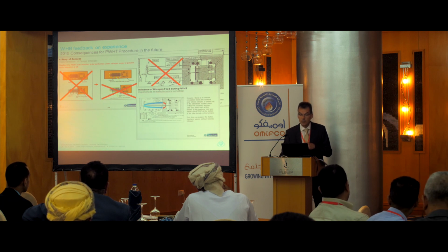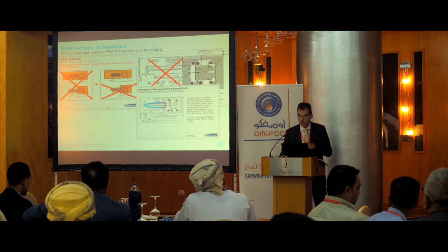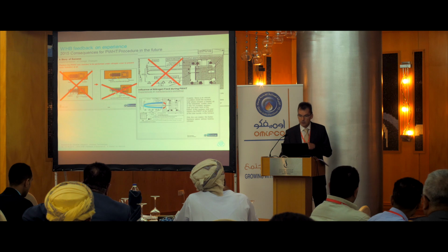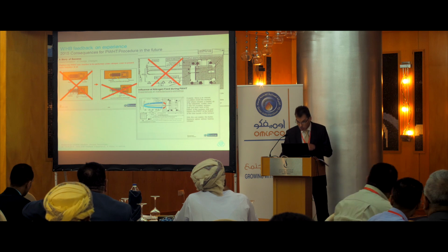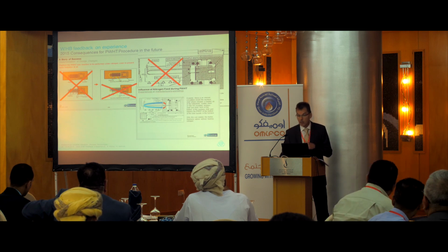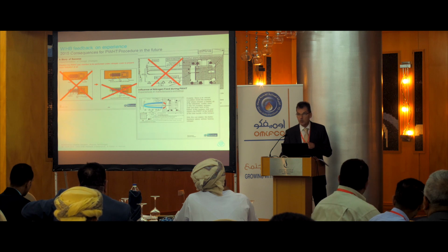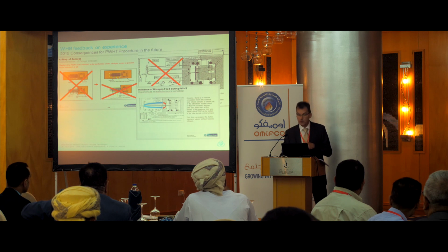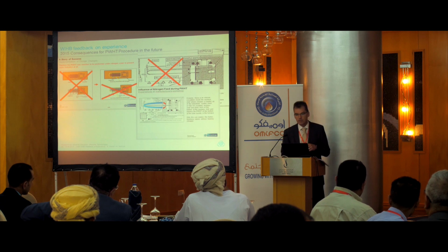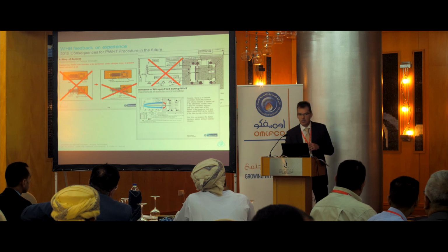Then we said, okay, if you have a furnace which has only a small size, you can do it, but you have to shield the outside bundle with an auxiliary shell, with nitrogen feed-in. This was now also forbidden because we recognized that when we have cracks and feed in nitrogen, we have the circulation shown here on the bottom side. So nowadays we only allow complete heat treatment of the equipment in one furnace with the auxiliary shell, with nitrogen feeding, of course, into the shell. And if the shell gets cracks, it doesn't matter. The pressure of the nitrogen outside and inside the furnace is nearly the same. Nitrogen will not disappear immediately out of this casing.